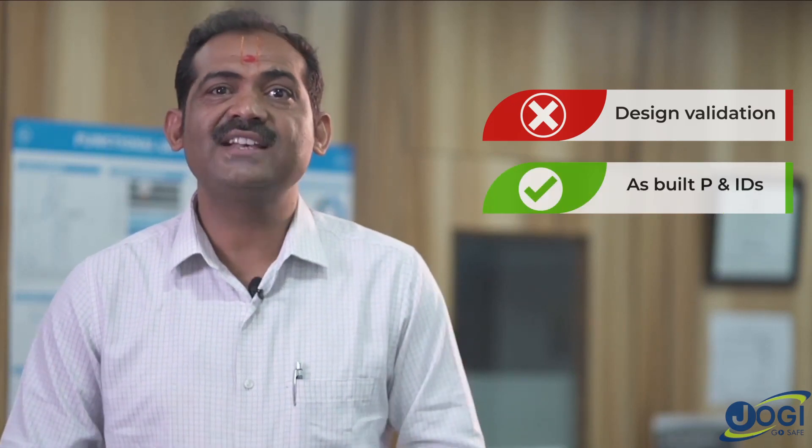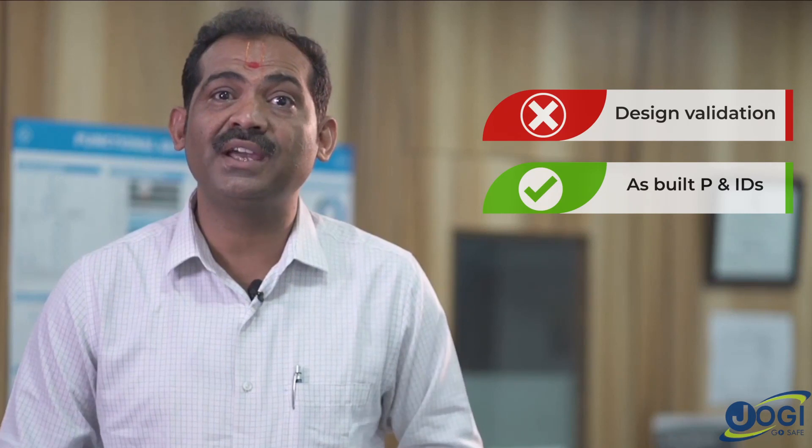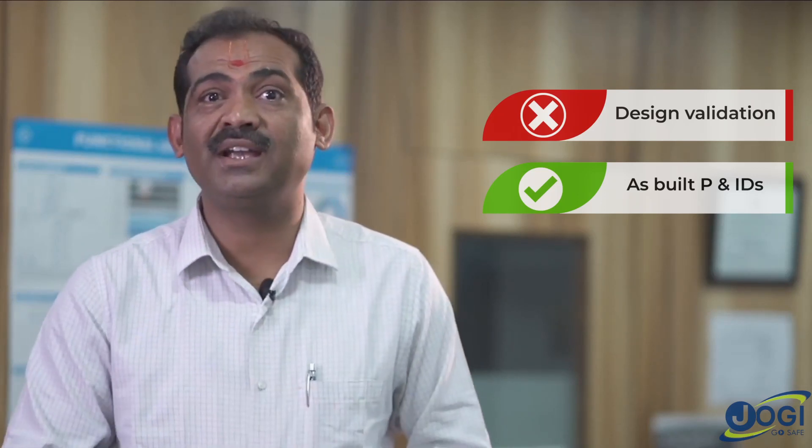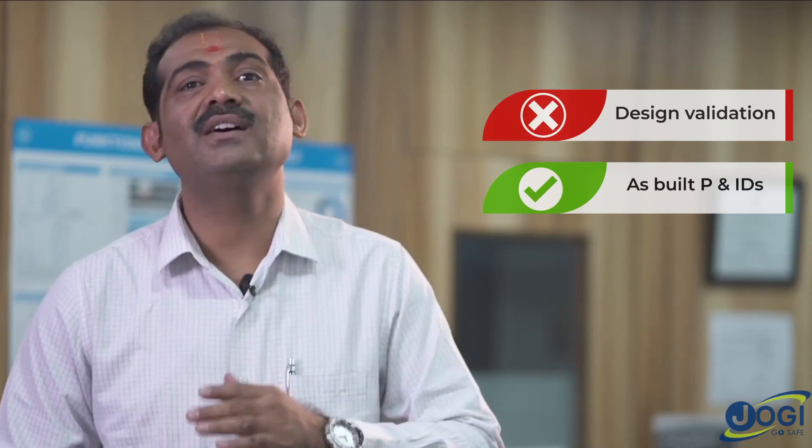Let me share some important limitations and do's and don'ts. First, HAZOP is not a tool for design validation — it is assumed that the design is adequate when the study is conducted. Second, P&IDs must be updated and as-built before the study, because anything that does not appear in the P&ID is not considered to exist on site.